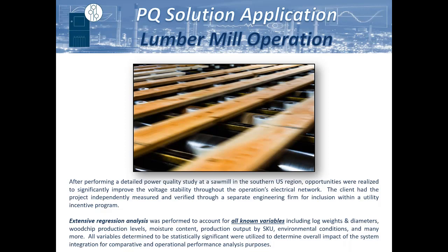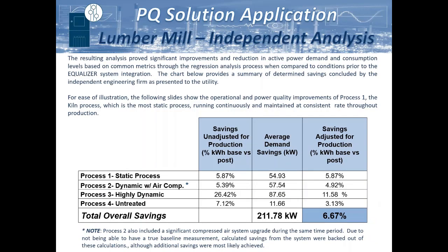And after looking at all of that information and accounting for production, they saw improvement even on their static processes, which is their kiln. If you know much about the lumber industry, the kiln is probably about 80 to 100 VFD fans all running at the same speed nonstop. Nothing ever changes. It's a very static process. And then you have the sawmill, which is very dynamic. And even in the main sawmill, they saw about 11.5% kW improvement, or efficiency improvement.